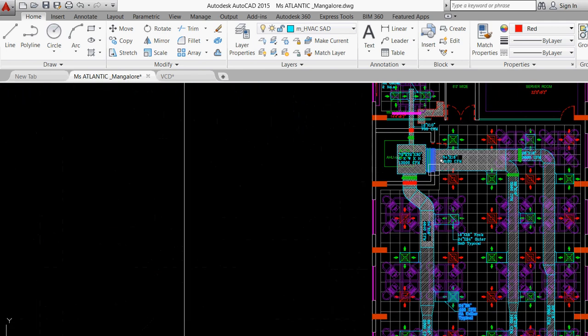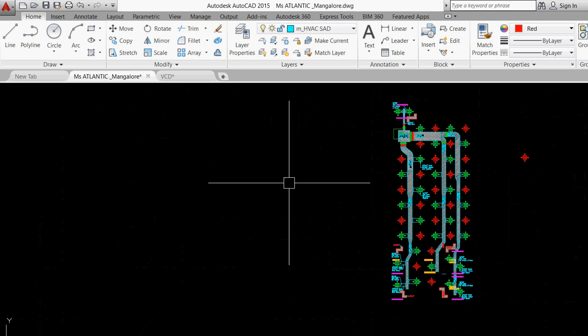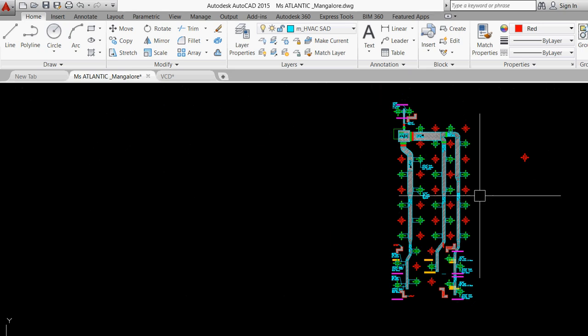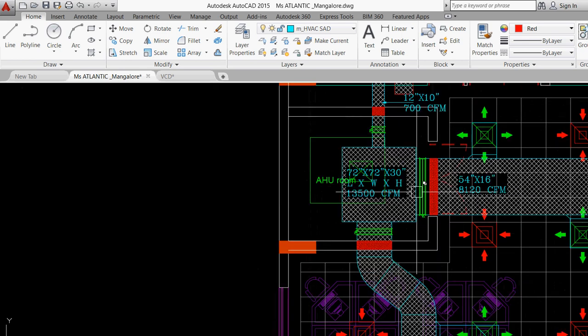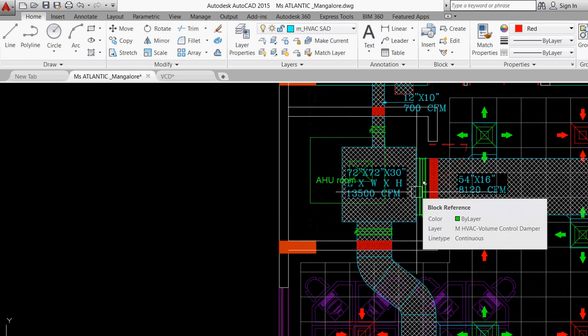Return air also we have to design. So this is the total thing that we have designed from morning. Clear? Understood or not from the afternoon session? Clear? So now the only thing is return air, which we have to really worry about. So for that, what I have to design now, the total CFM is 13,500 CFM. Now don't you think you have to fit the remaining thing as your return air path? And now those locations have to provide a fire damper also. You remember? Supply and return both have to provide my fire damper.